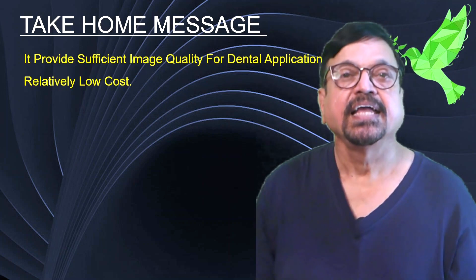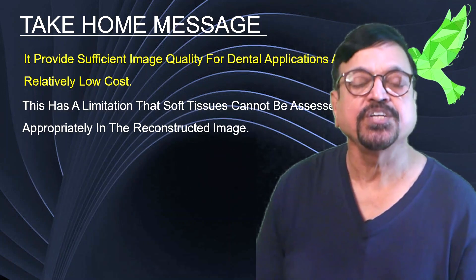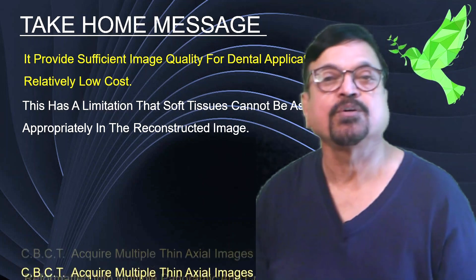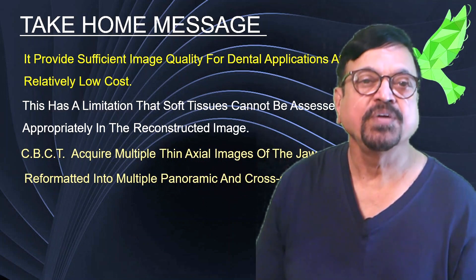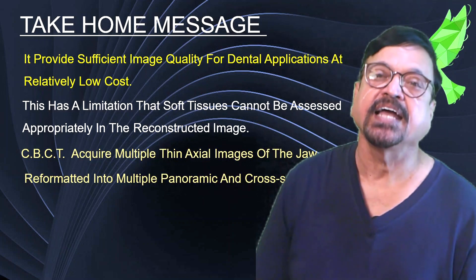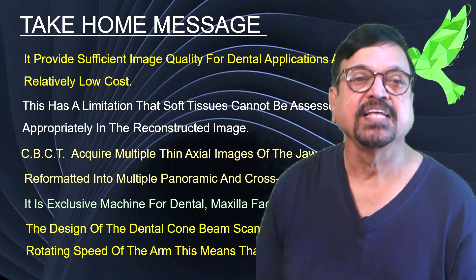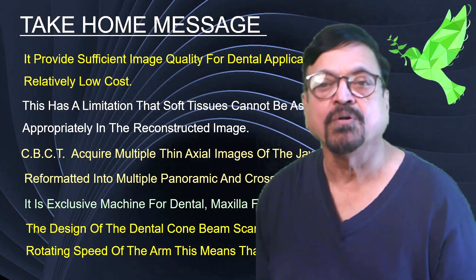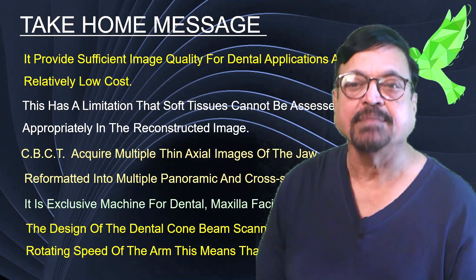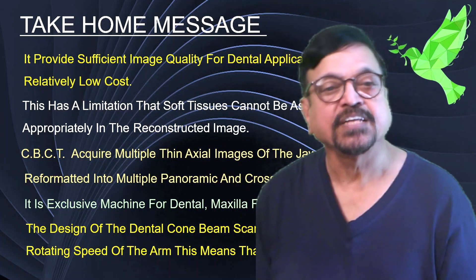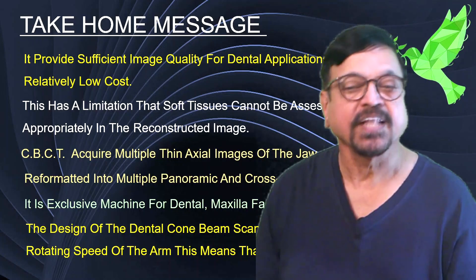Take-home messages: CBCT provides sufficient image quality for dental applications at relatively low cost. It has limitations regarding soft tissue, which cannot be visualized as well as bone. CBCT acquires multiple thin axial images of the jaw which are reformatted into multiple panoramic and cross-sectional views. It is an exclusive machine for dental and maxillary applications. The design of dental cone beam scanners limits the rotating speed of the arm, meaning rotation time is relatively long — it must rotate 360 degrees and does so slowly because it does not have slip rings like a conventional CT machine.